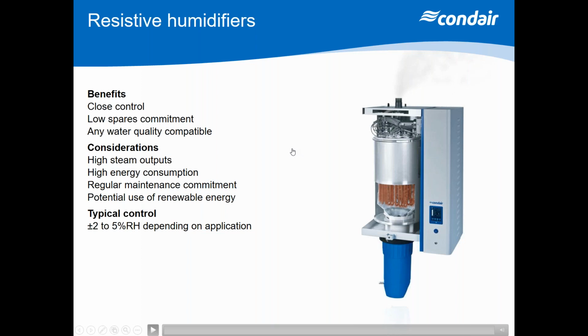conductivity. So in a low conductivity area, I can use them. And in a high mineral content area, if I want to reduce the amount of maintenance, I can feed it with RO water. Steam capacities are very similar. They start at 5 and they go up to 160 kilos an hour with 4 boiling cylinders. I do have to consider, of course, the energy consumption because for every 100 kilos of steam we're producing, it's 75 kilowatts. And of course, there is a regular maintenance commitment. Again, we can use renewable energy. So again, it's really important to specify the type of humidifier that you're going to be using because the ramifications of getting the wrong one are really significant.